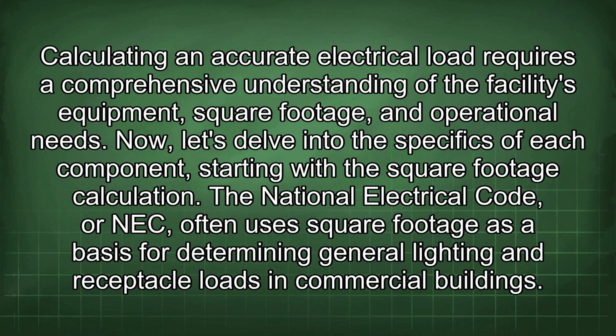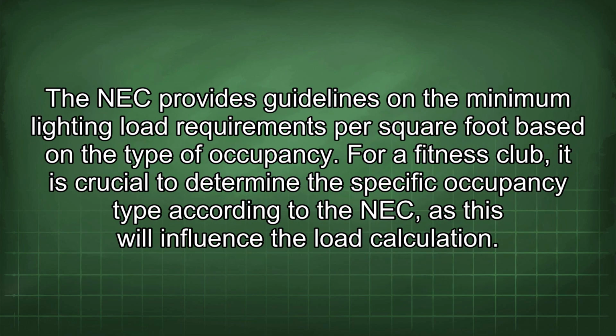The National Electrical Code, or NEC, often uses square footage as a basis for determining general lighting and receptacle loads in commercial buildings. The NEC provides guidelines on the minimum lighting load requirements per square foot based on the type of occupancy. For a fitness club, it is crucial to determine the specific occupancy type according to the NEC, as this will influence the load calculation.